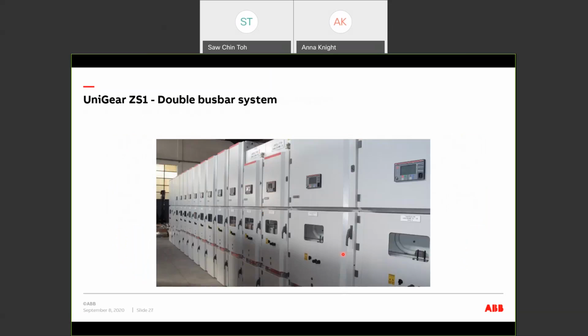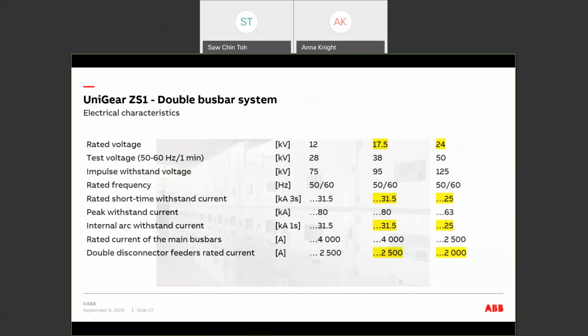UniGear ZS1 is also designed for double busbar systems. This is mainly used in utilities. The rating of the panels is 17.5 kV, 31.5 kA, and 2,500 amps maximum, or 24 kV, 25 kA, and 2,000 amps maximum.